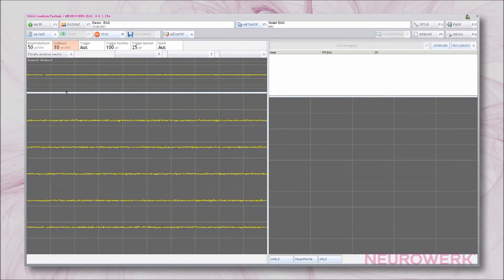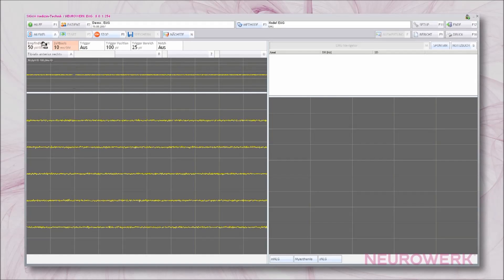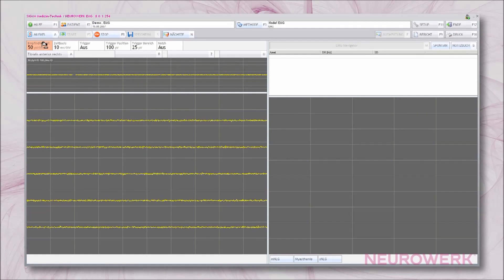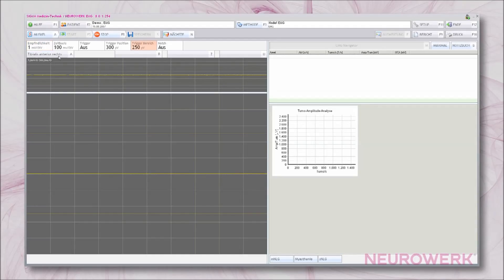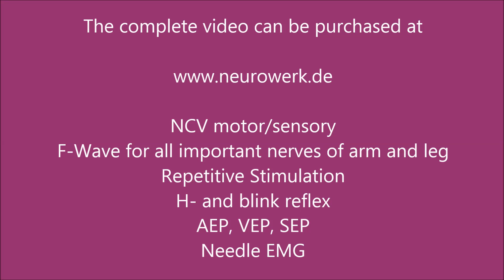The instrument settings for the needle EMG examination should be selected as follows. The amplification is 50 microvolts per division in spontaneous activity, 100 microvolts per division in arbitrary innervation, and 1000 microvolts per division in maximal innervation.